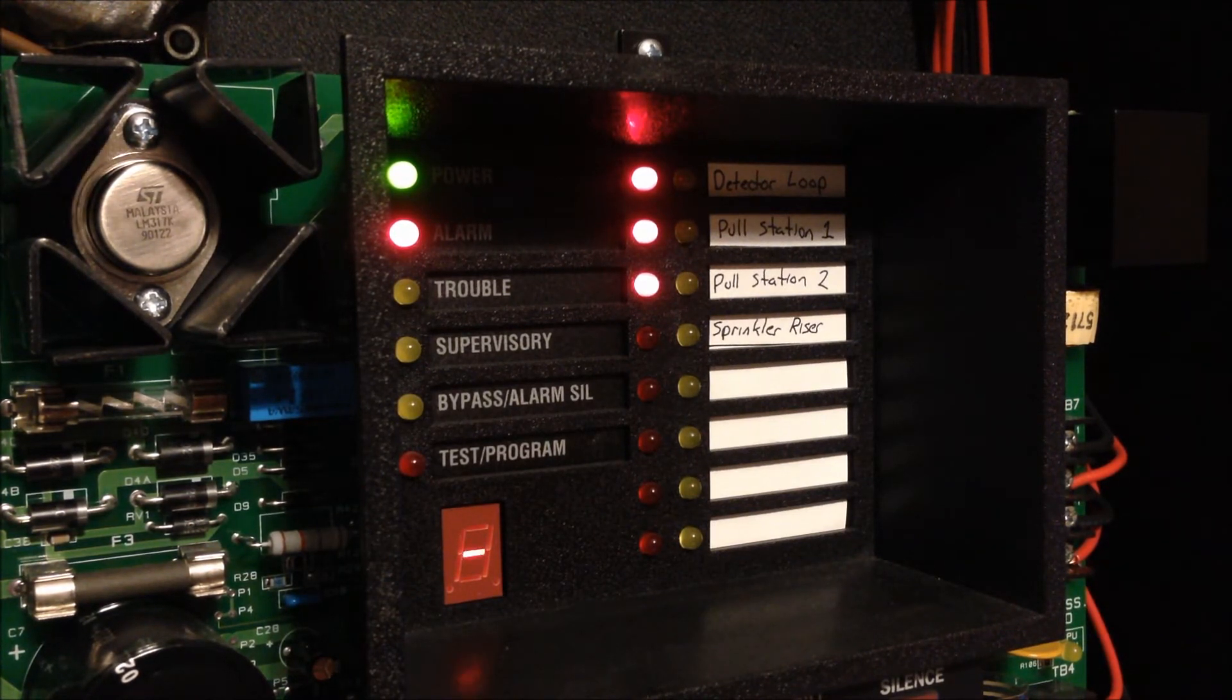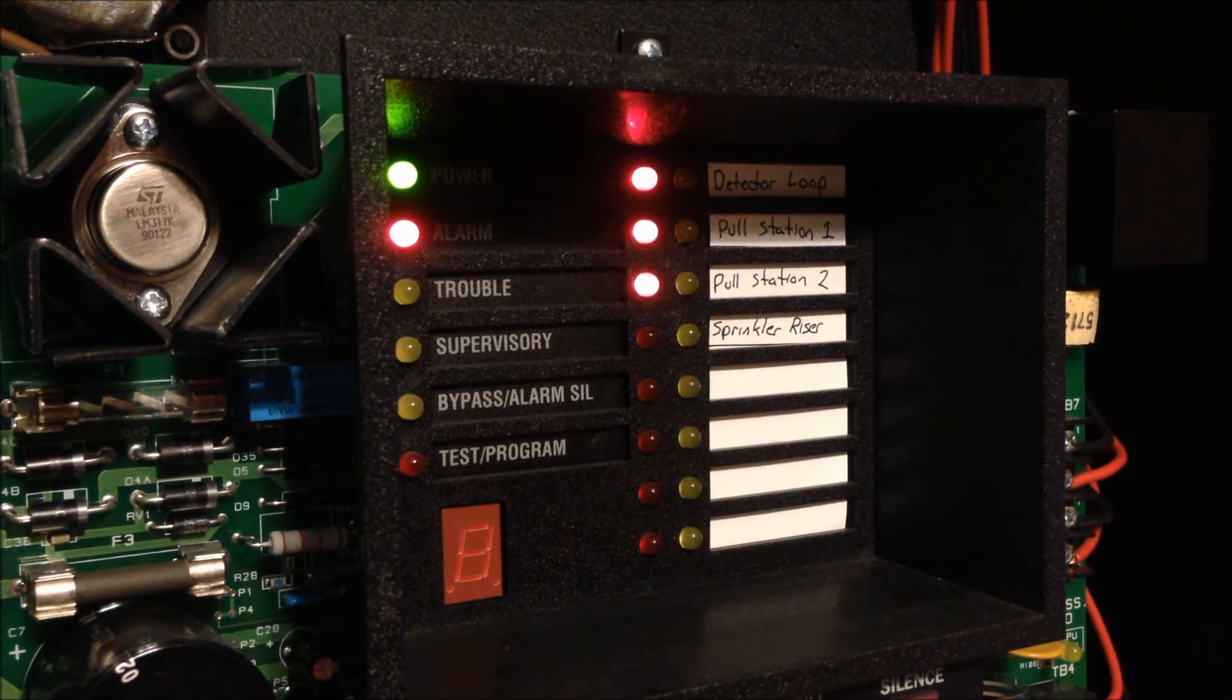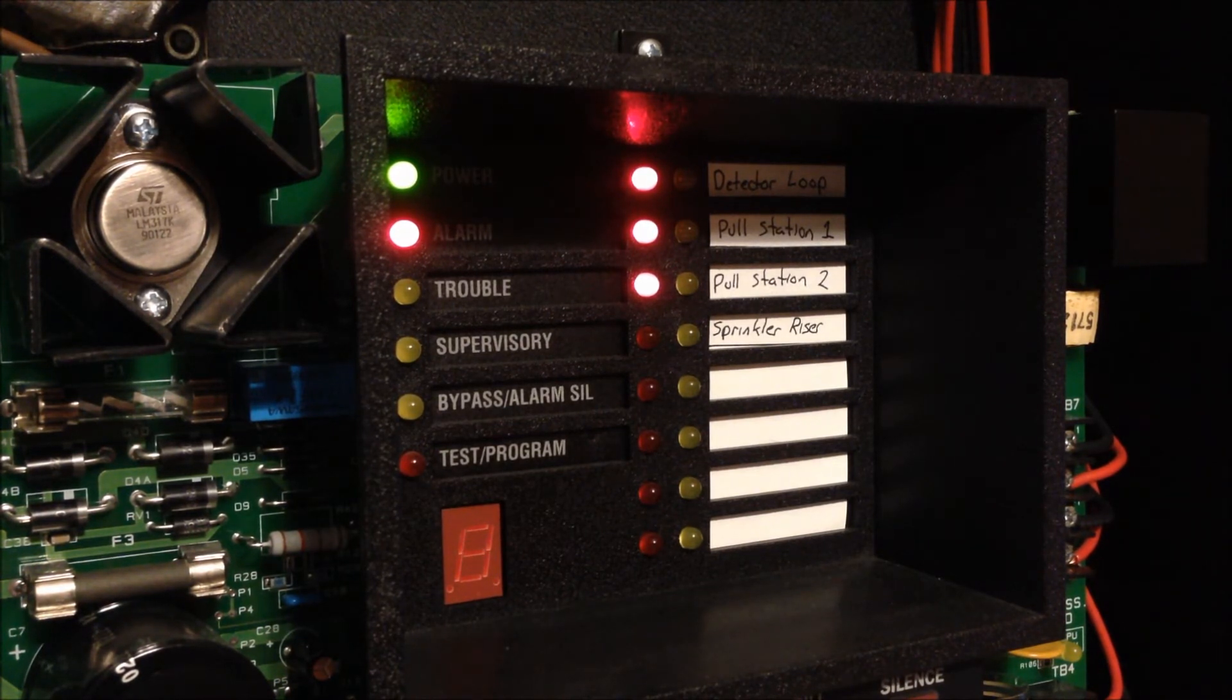Now when I go to silence these I'm actually going to have to silence it 3 times to silence each of the alarms from the 3 zones.